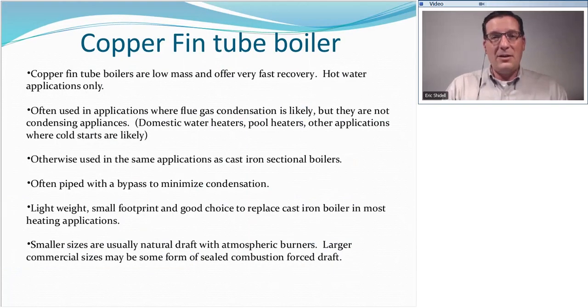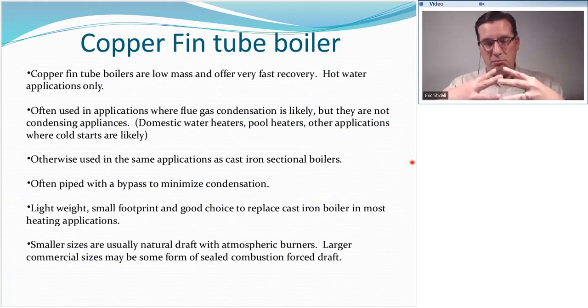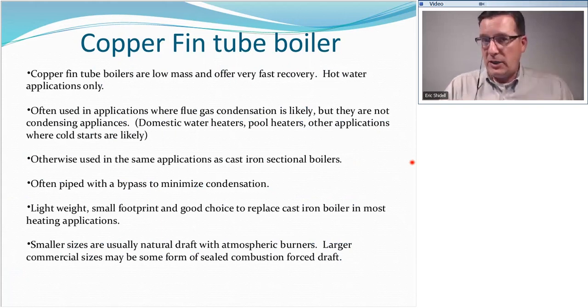Some of the notable features of the copper fin tube boiler are, number one, they are very low mass, which offers very fast recovery. They can heat up to temperature very quickly because there's not a whole lot to them. They're generally hot water applications only, no steam. Also, no oil, no solid fuel. Natural gas only on copper fin tube boilers. They're often used in applications where flue gas condensation is likely under certain conditions, but they're not meant to operate in a condensing fashion permanently. Doing so is going to cause damage.